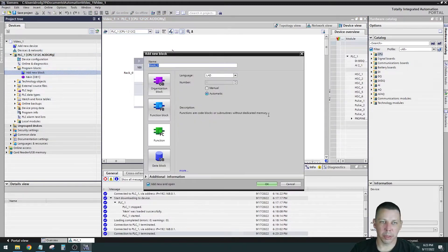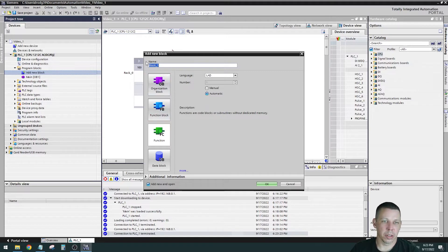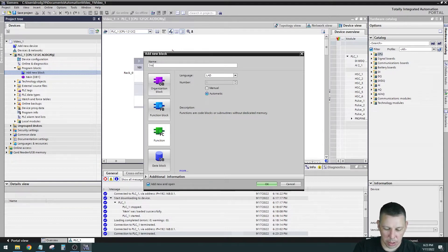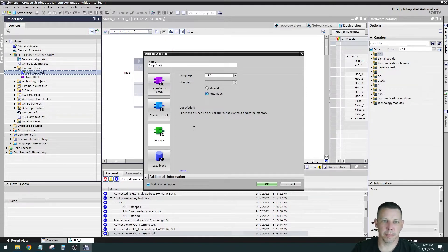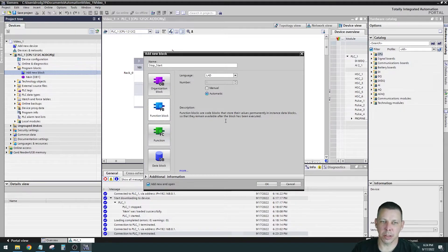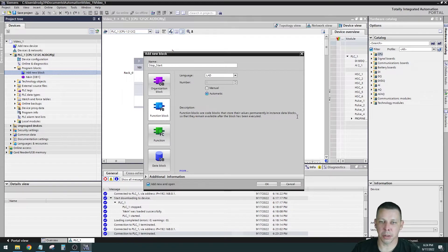We're going to add a new block. You can choose an OB, a function block, a function, or a data block. If you select them individually it'll give you a description. I'll call this one 'stop start'. If you go to Function Block, it says function blocks are code blocks that store their values permanently in an instance data block. So if you have a timer or counter that needs to keep a running total or accumulated value between scans, you'll need a function block — it has a data block as a memory location.